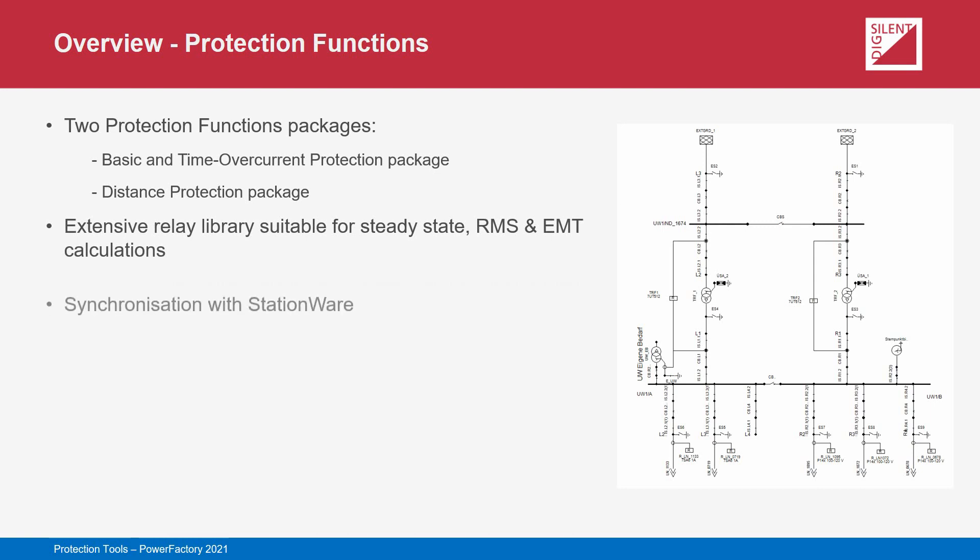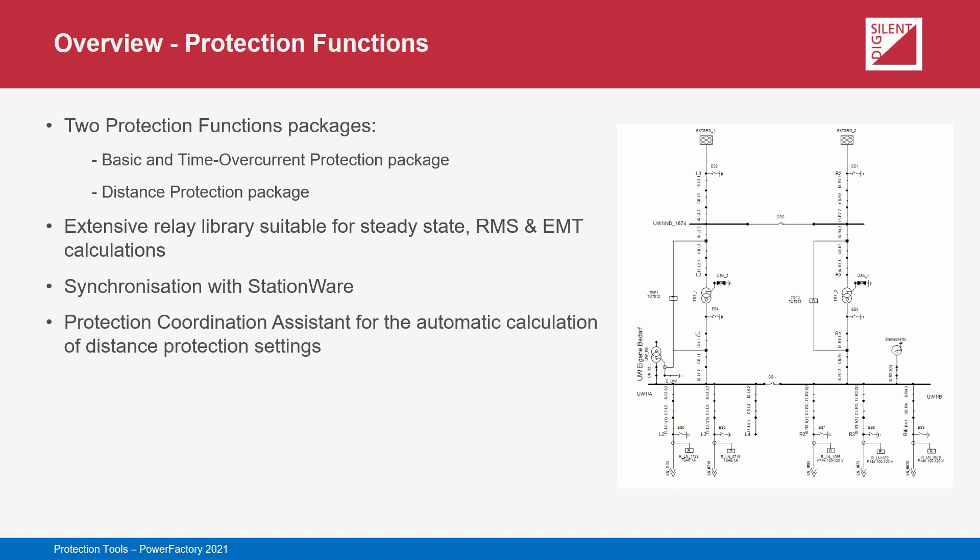The protection device models are highly detailed and are completely aligned with DIgSILENT's centralized protection setting database software, StationWare, thereby promoting the bidirectional exchange of settings with real protection devices. Once relays have been included in the PowerFactory network model, advanced tools such as the Protection Coordination Assistant and the Protection Audit can be used to analyze and optimize relay settings. For example, the Protection Coordination Assistant can be used to apply user-definable setting rules for the automatic calculation of distance protection reach settings.